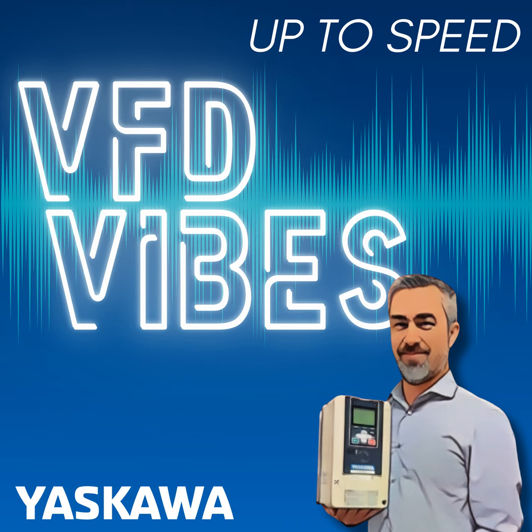As someone put it to me one time, if you get noise into the cable, it could delay a message from getting from point A to point B. And the way most networks operate is if they can't interpret the signal coming in when they do their checksum on the data, depending on the type of network, they'll either re-request it or just drop it and wait for it to come in again. Based on your RPI settings and how fast the system expects that data to come in, if it doesn't see it after so many milliseconds or so many dropped packets, it will actually fault out the entire system.